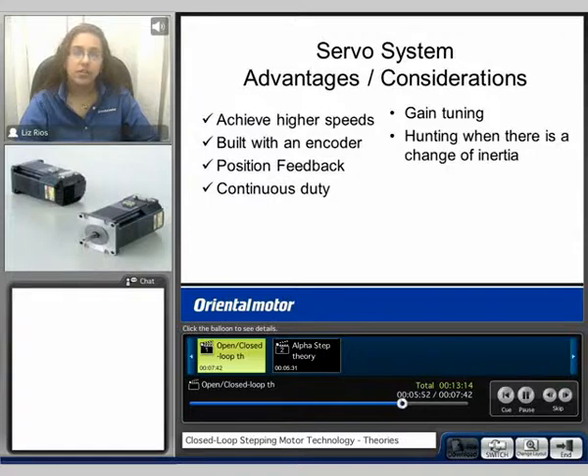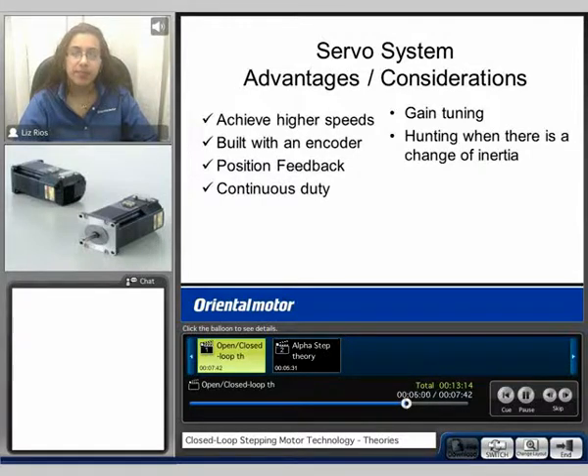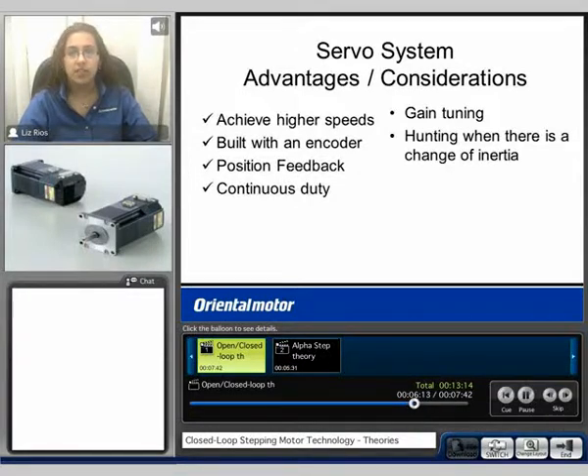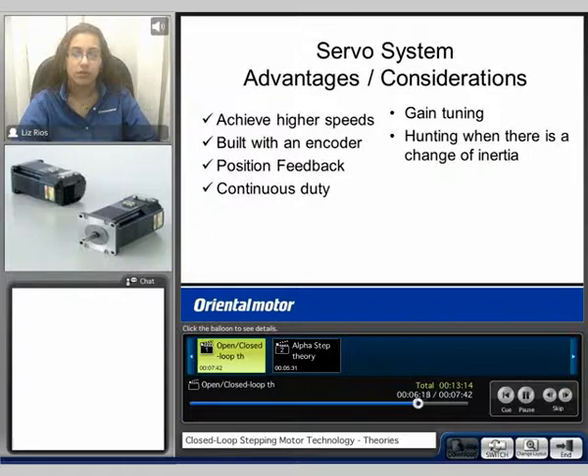Here we can take a look at the servo system advantages and considerations. The servo system can achieve higher speeds. It is built with an encoder, so it is a closed loop system and you do have positioning feedback. It is also rated for continuous duty. Some considerations are the gain tuning — the overall performance of the servo system is based on the gain value — and hunting when there is a change of inertia load.